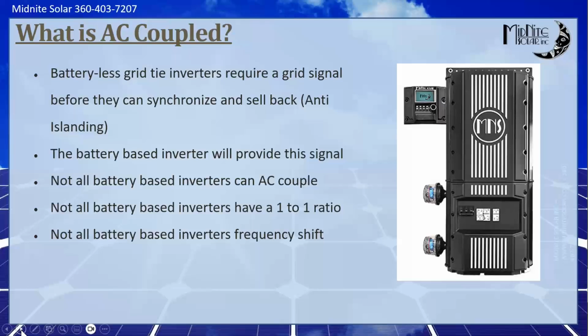But some inverters just won't frequency shift, and for the ones that won't, you need to do some form of a blackout relay on the grid tie inverter that will kick it offline or remove its grid reference when the battery is full. What we used to do on products before we had the Rosie, we installed a 2-pole relay in there and we drove it from one of the auxiliaries. When the battery voltage exceeded a set point, we would open that relay and disconnect the grid tie inverter.